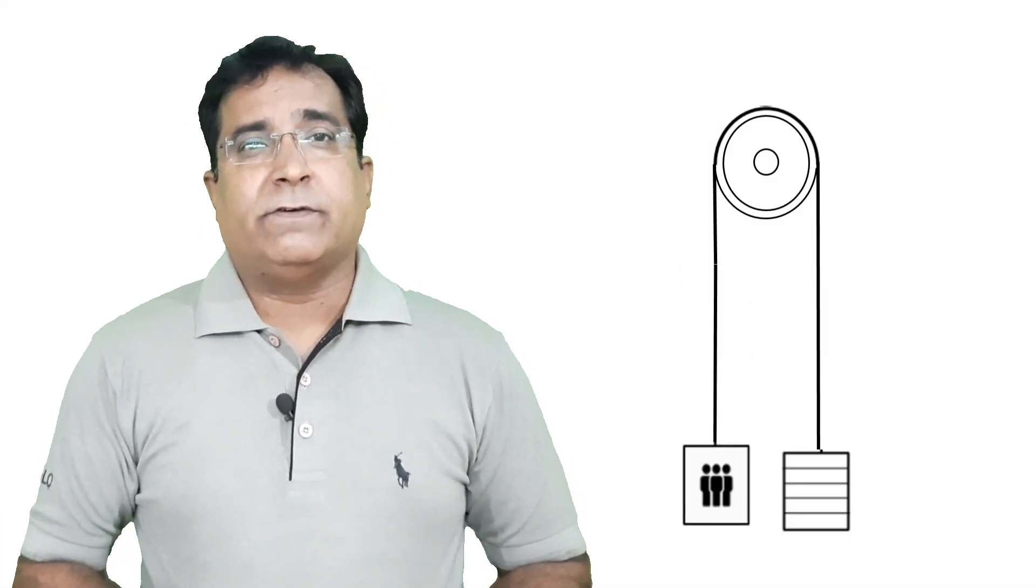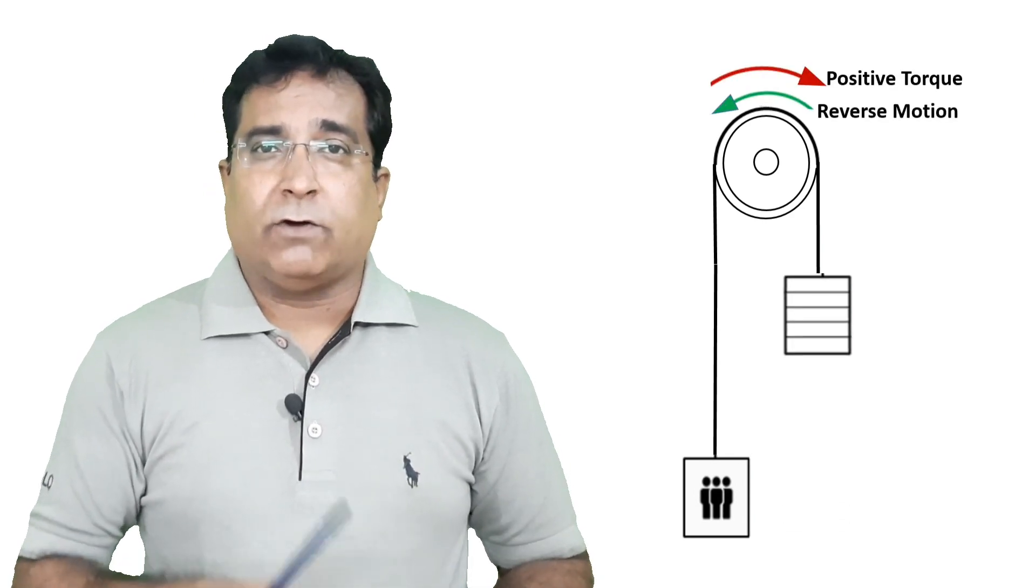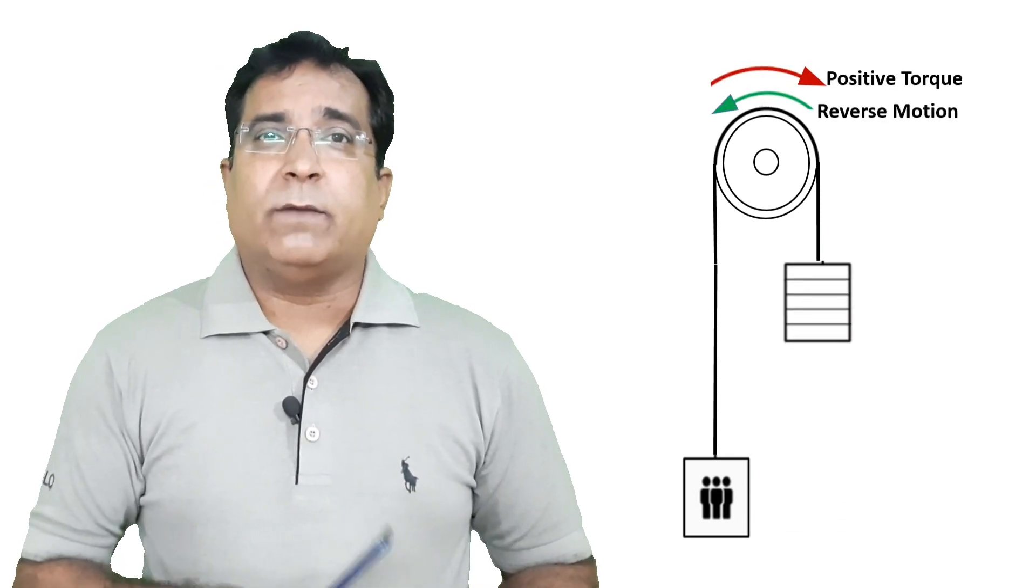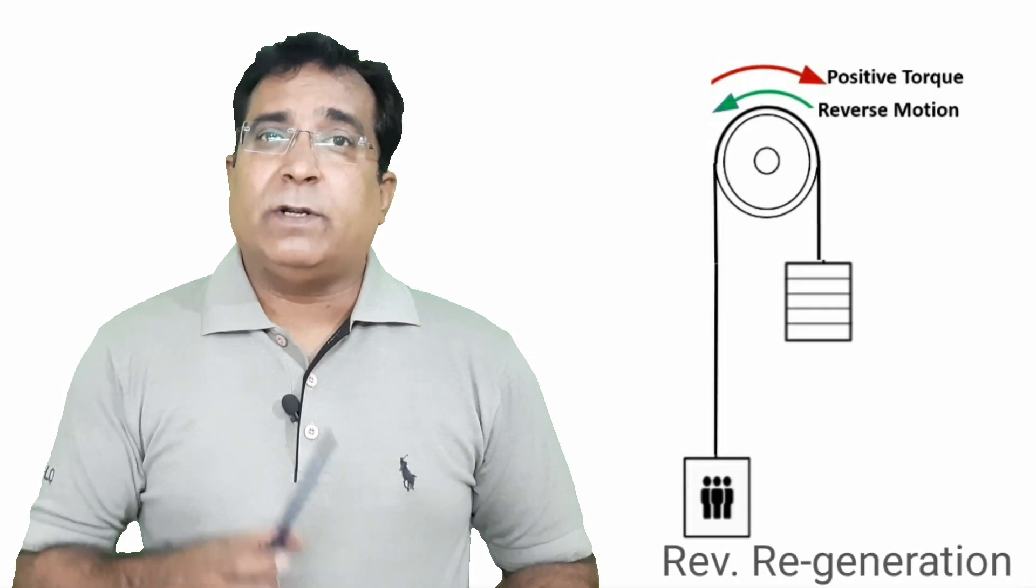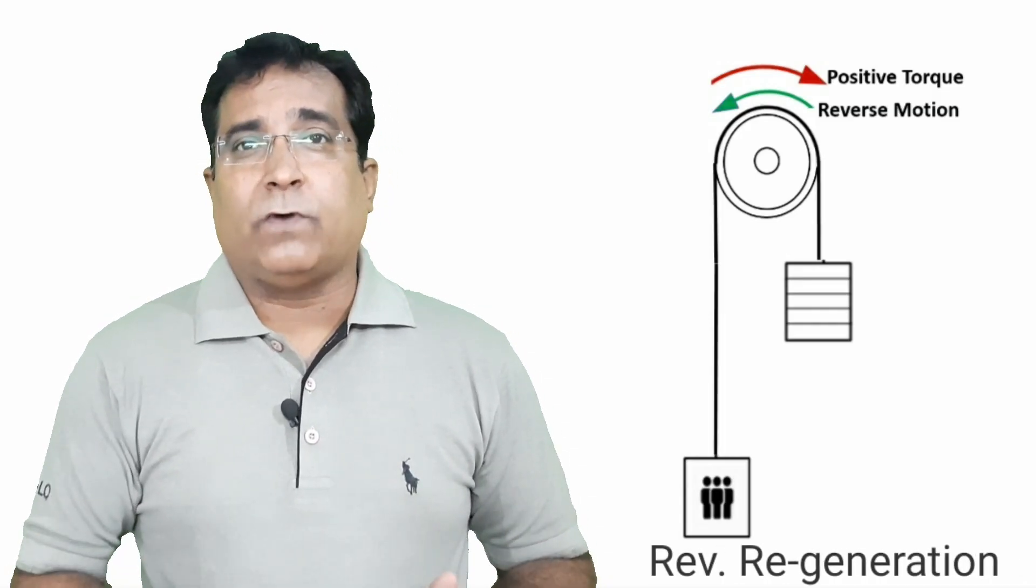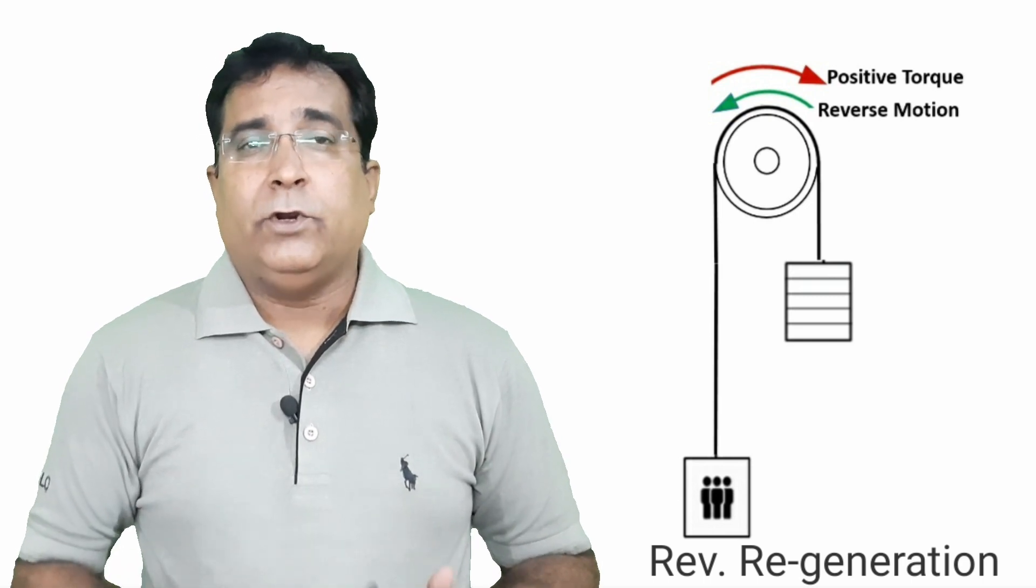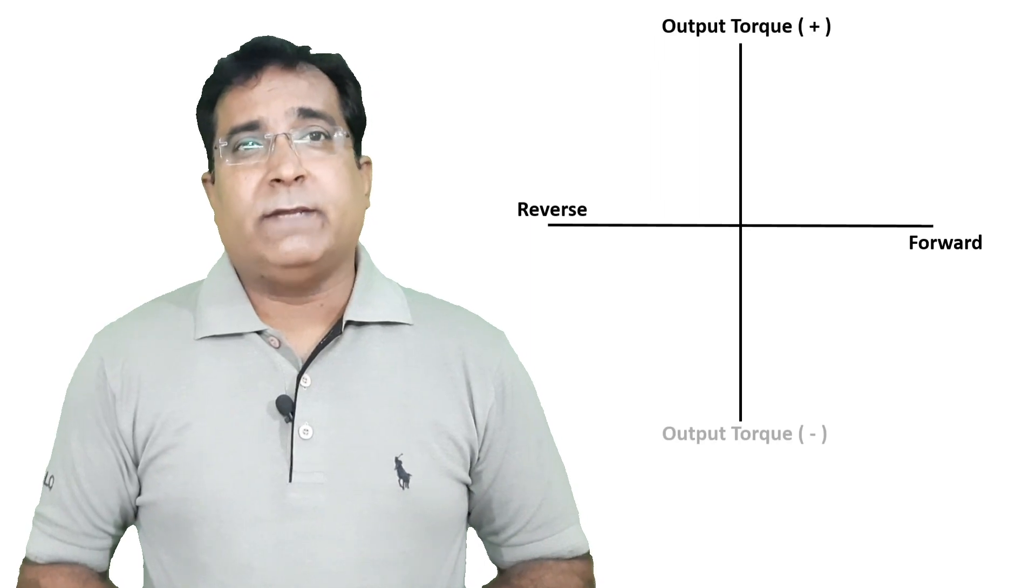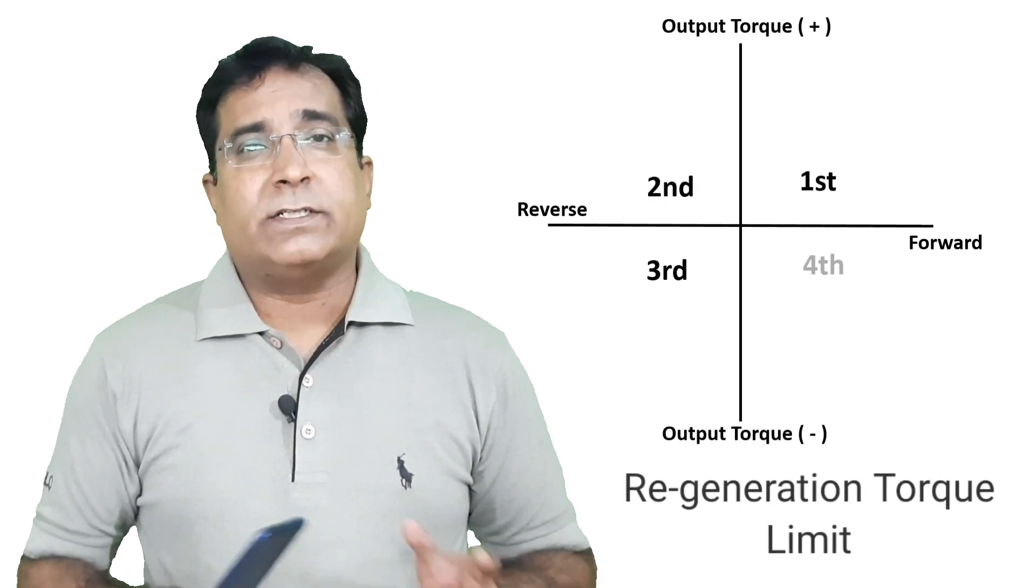Now let us check out the first situation when the car is full of passengers and has to come down from top to bottom. Obviously motor needs to be run in reverse direction and the weight of car is more than the counterweight. Again role of gravity comes into picture. The full car will pull the motor so the motor will be in regeneration, but the car is not supposed to fall suddenly on ground due to gravity.